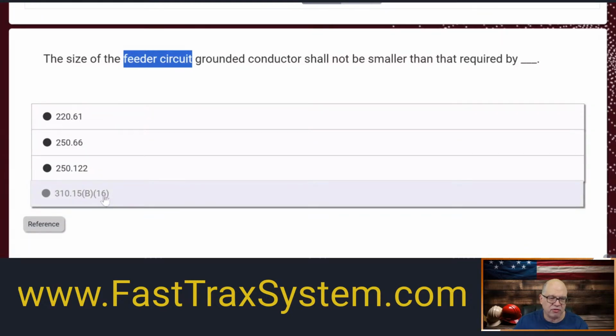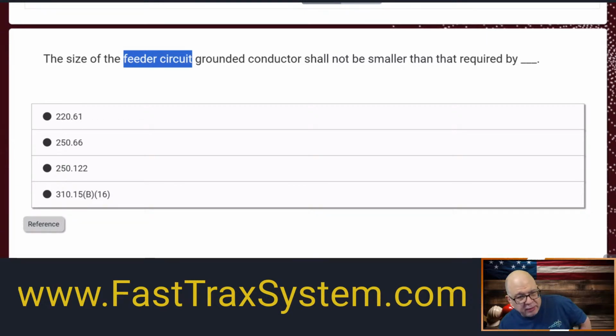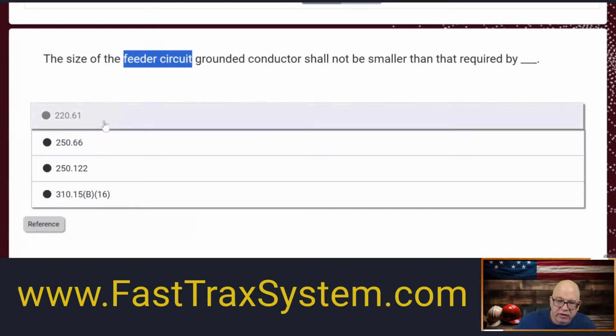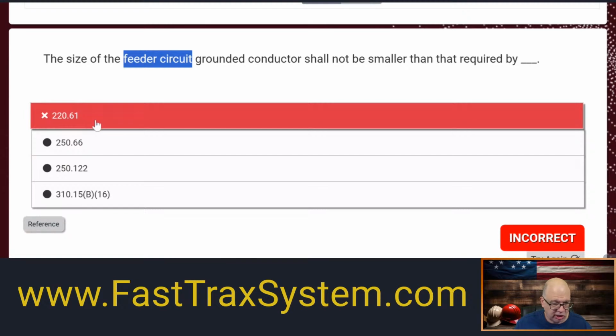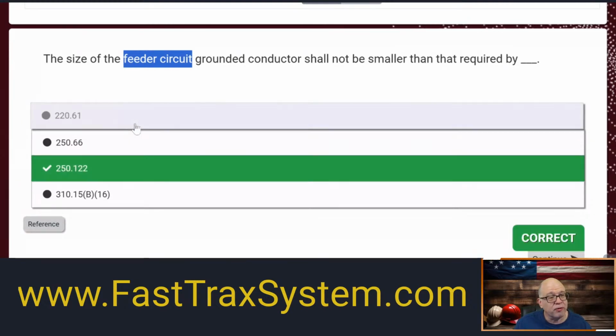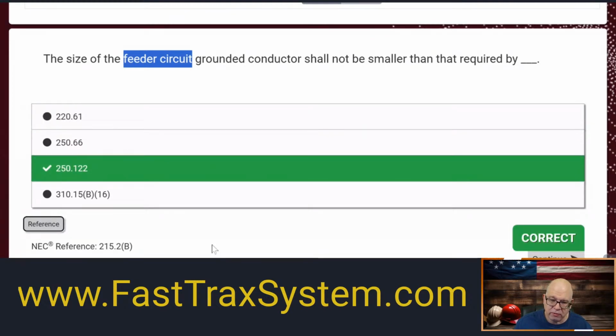And you could have thrown this out because it's just an ampacity table. It's really not even relevant in the 2023 edition because it's 310.16 actually. So in this one, you could have gone to, but that doesn't really answer the question. But if you were looking at it really quickly and you weren't thinking about it, and you're like, dude, I just want to answer this damn question, I've got to get going, then you might have said, oh, I know that the feeder grounded conductor is sized in 220.61, and you would have gotten it wrong. You ready? Watch. Wrong. Your answer is 250.122. And here's your reference, 215.2(B).